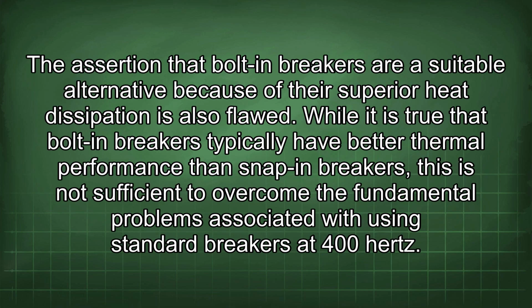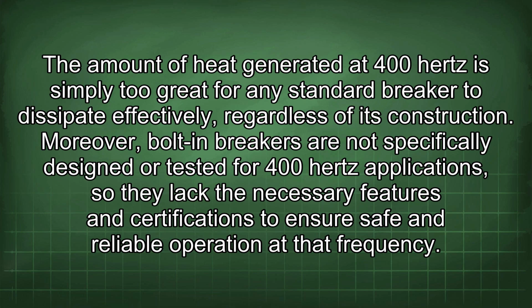The assertion that bolt-in breakers are a suitable alternative because of their superior heat dissipation is also flawed. While it is true that bolt-in breakers typically have better thermal performance than snap-in breakers, this is not sufficient to overcome the fundamental problems associated with using standard breakers at 400 Hz. The amount of heat generated at 400 Hz is simply too great for any standard breaker to dissipate effectively, regardless of its construction. Moreover, bolt-in breakers are not specifically designed or tested for 400 Hz applications, so they lack the necessary features and certifications to ensure safe and reliable operation at that frequency.